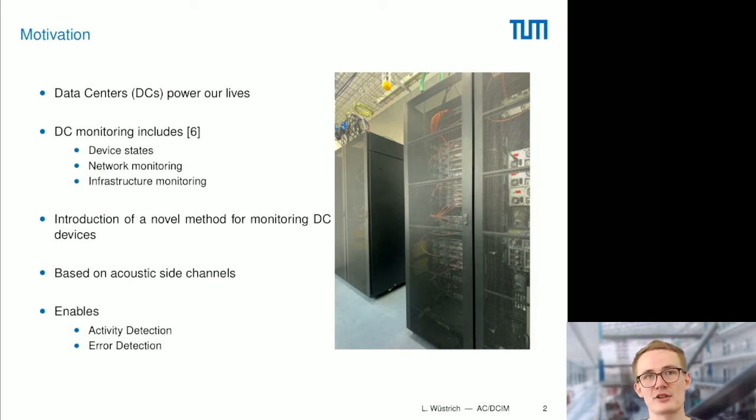The monitoring itself consists of several components that observe device states, network communication, and the infrastructure of a data center. While device states and network communication can be monitored from within a system, infrastructure monitoring often requires additional hardware to measure the physical environment of data centers. We propose a novel method to monitor data center devices and infrastructure based on acoustic side channels. Our experiments indicate that the proposed approach enables activity detection of single devices in a mixed signal and even the detection of error beep codes emitted by a server board.